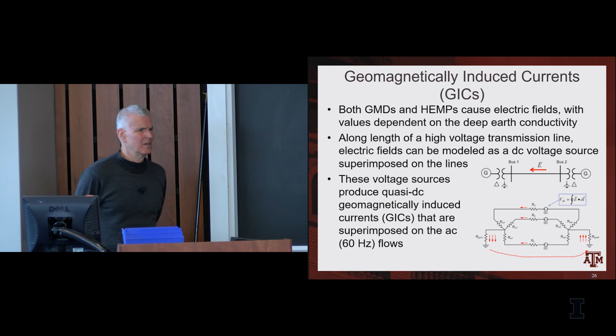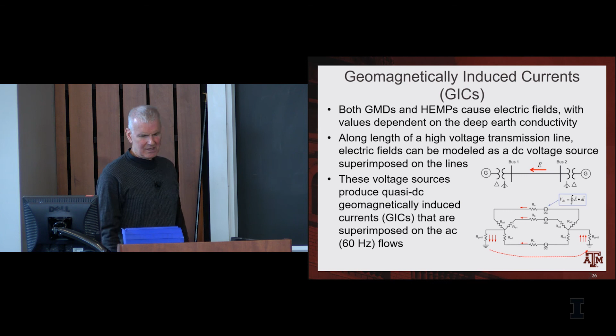How they impact the grid is these GICs, or low-frequency currents, flow through the grid, because at low frequency the high voltage grid looks kind of like a DC circuit. The three phases are in parallel, so it looks like three lines in parallel. The GICs superimpose on the AC flows, and we can calculate how these GICs flow through the grid.